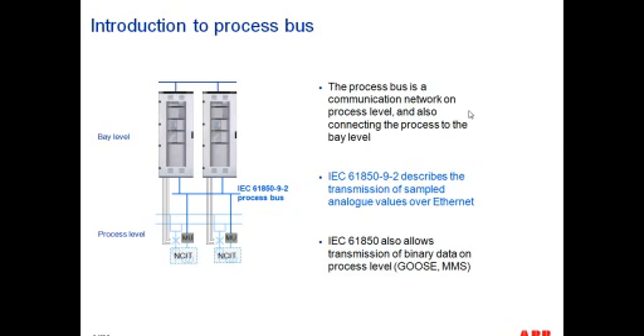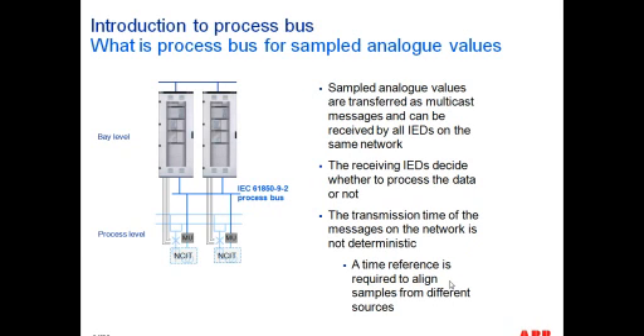So the process bus is a communications network at the process level, as mentioned, also connecting the process to the bay level. IEC 61850-9-2 describes the transmission of sampled analog values over Ethernet. And as I mentioned, IEC 61850 also allows the transmission of binary data at the process level via GOOSE messages. Sampled analog values are transferred as Ethernet multicast messages, and can be received by all IEDs on the same network, based on the configuration of that network, of course. The receiving IEDs decide whether to process the data or not. And what that means is that is the process the relays use to either subscribe and consume that information or not subscribe and decide not to consume that information.